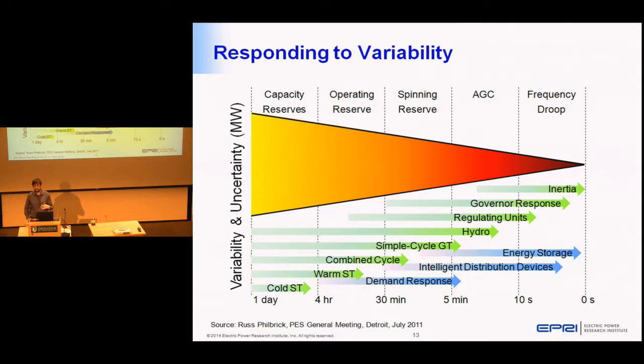That's what they do in a lot of systems. Traditionally, they might only decide every 30 minutes and then leave everything automatic from then on. That's because it was easier—the computing power and communications technology may not have been there. But now we've got that type of computing power and communications technology, so it's worth putting online. Making decisions closer to real time and more frequently will significantly help accommodate a lot of the variability and uncertainty, without having to install any new devices.